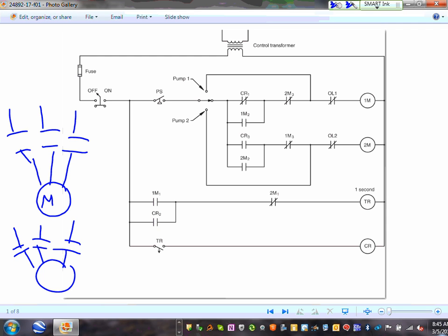So this is M1, machine one, and this is M2. In a lifting station, if you have a lift station, they have two pumps. Any one pump can handle the load of pumping all the water or sludge water. But they want to alternate them. So these are M1 contacts and M2 contacts. And I don't want to use PLCs because I'm cheap — I want to use relay logic. Look how you do it in relay logic.